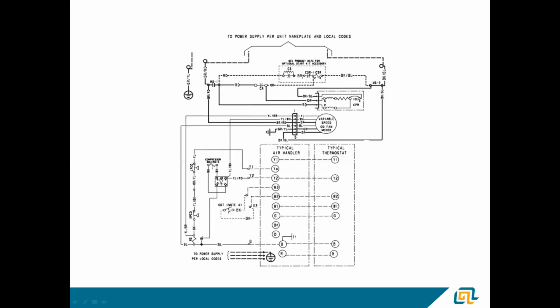When I pulled this drawing out, what I noticed, and I hadn't seen this before, this is something new to me. This is actually a 2-speed fan motor. If you notice, you've got a yellow and brown wire bringing our Y1 signal to the motor. So if it's energized on yellow and brown, the motor would understand that it's in first stage cooling, and it would probably run at a slightly lower speed. Then we've got another lead here, yellow and white, coming off our Y2. This is our Y2 coming in, comes off the little rectifier, comes up to the motor here, and that energizes the motor to run in high speed. So you see something like this, you got a 2-speed motor there.